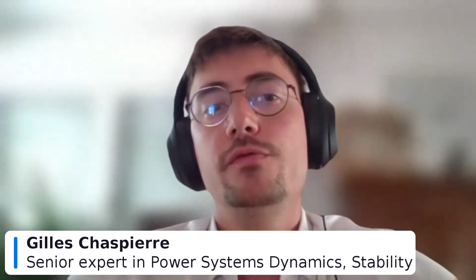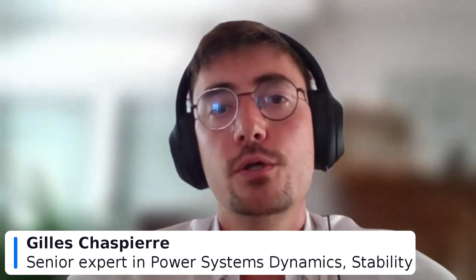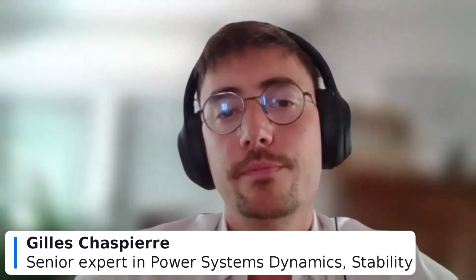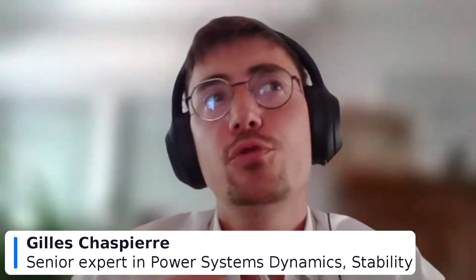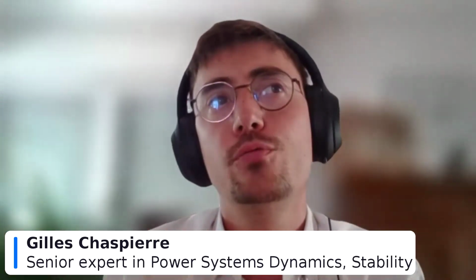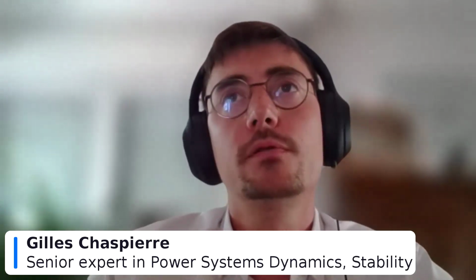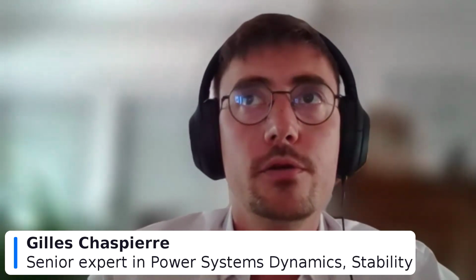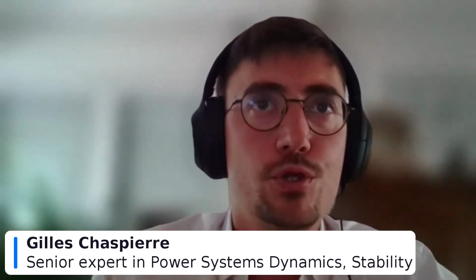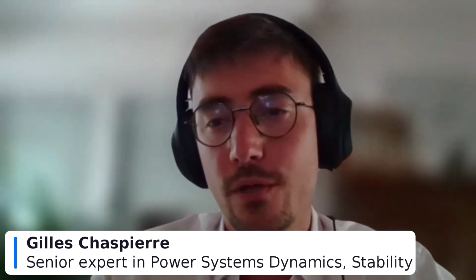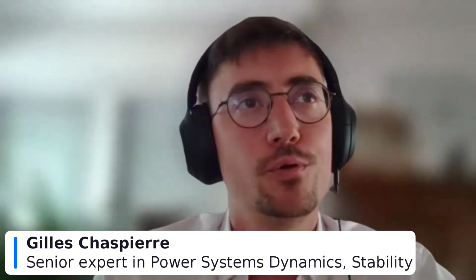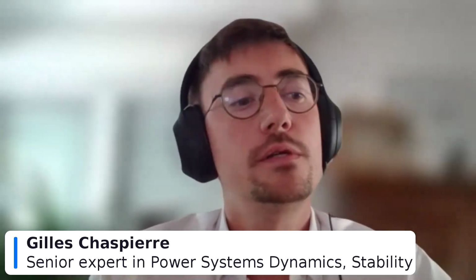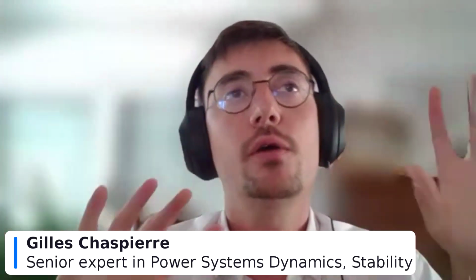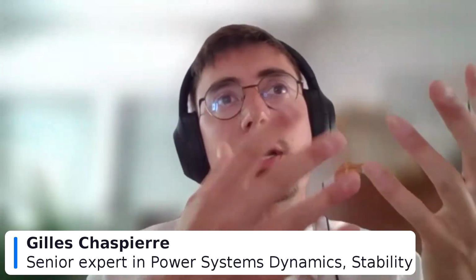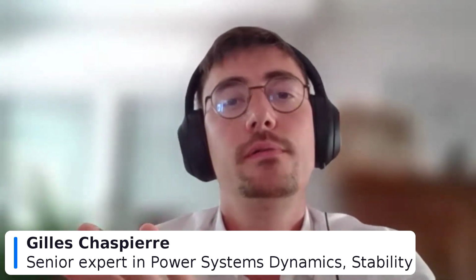The major difference between synchronous condensers and SVCs, for instance, is that a synchronous condenser will actually increase the system strength, but you might overinvest. If you only need reactive power capability, you might overinvest in something. So what I would recommend is to develop relevant indicators, like we discussed the short circuit ratio. If you are interested, you can always contact me on LinkedIn, and I will direct you to other material. There are a lot of possible indicators that TSOs or system operators can use to spot areas where synchronous condensers are needed versus only reactive power margin.